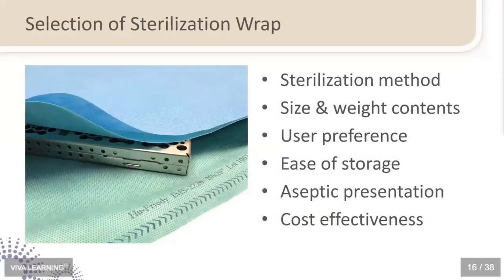We're going to move out of pouches and into sterilization wrap, and we are seeing an increased use of instrument management type systems, cassettes, and the use of sterilization wrap. It is possible you may choose to put cassettes inside pouches. You need to make sure that that particular cassette has been approved for use inside a sterilization pouch.